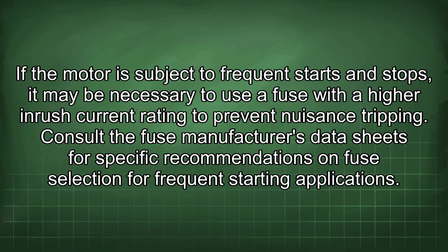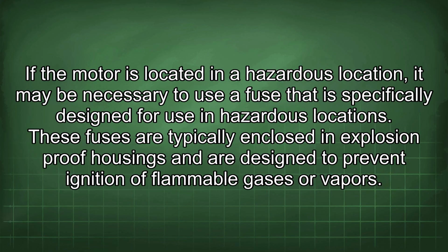If the motor is subject to frequent starts and stops, it may be necessary to use a fuse with a higher inrush current rating to prevent nuisance tripping. Consult the fuse manufacturer's data sheets for specific recommendations on fuse selection for frequent starting applications. If the motor is located in a hazardous location, it may be necessary to use a fuse that is specifically designed for use in hazardous locations. These fuses are typically enclosed in explosion-proof housings and are designed to prevent ignition of flammable gases or vapors.